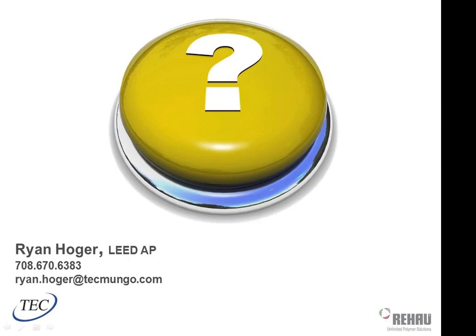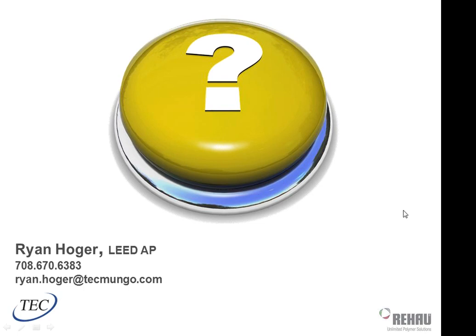All right, let me check real quick if there are any last questions, and then I'll cut you guys loose because I know I've talked over my time here. All right, we do have a question from Ali. You mentioned that chilled water temperature should be above space dew point. I'm assuming we're talking about a radiant cooling system again. It can be a little less than the space dew point as long as the surface temperature of the floor is above dew point. Is that correct?